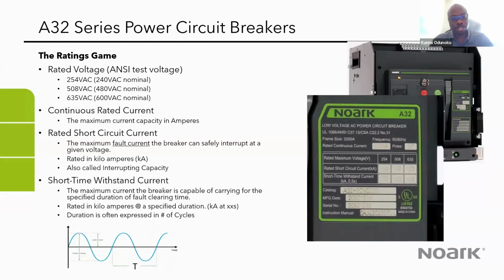What this coordination does is that it helps to isolate the fault to the faulty feeder. What you do with the current withstand is introduce a delay in the reaction of that air circuit breaker, so that the breaker that is closest to the fault is the one to react to that fault. If that breaker is not successful in doing that, then the next level breaker will be the one to respond to the fault. This helps the system isolate faults quickly and keep continuity of service, so you don't affect feeders that are healthy. If the main breaker reacts to every fault, the healthy feeders will also lose power at the same time as the faulty feeder.